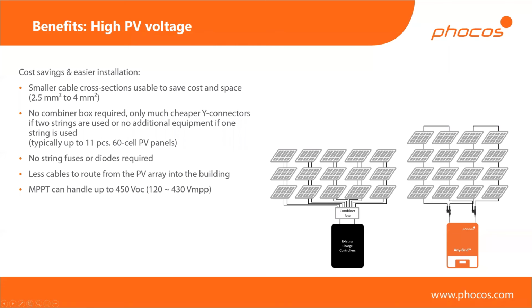So some other benefits of this higher PV voltage are you have much smaller cable cross sections to deal with. Coming from a combiner box, if you're dealing with 5 kilowatts at, let's say, around about 100 volts, you're going to be dealing with 16 millimeters squared. I'm not sure what that is in American wire gauge, but it's definitely a lot more. It's about 4 times as much than what we have here.